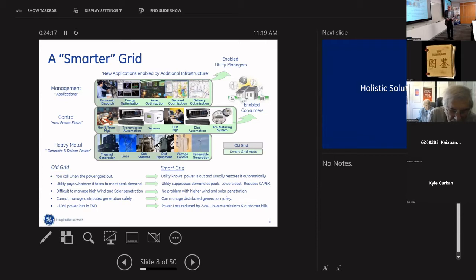We have specialized sensors that we're adding to the grid, things we didn't have before. There's a new family of sensors called monitoring and diagnostic, M&D. If I take the oil from the main tank of the transformer and bring it through that sensor, I can detect up to 9 different gases dissolved in that oil. That's very important today because we don't want to be reactive anymore. Reactive was where we waited until a transformer exploded and destroyed the whole substation.